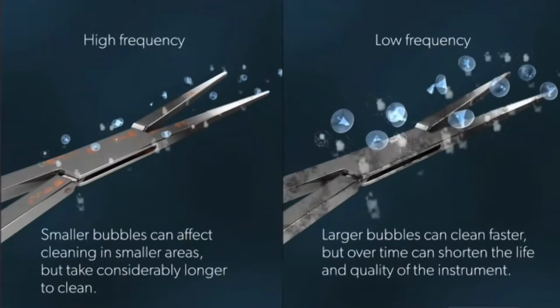Let's break down this cavitation energy, particularly in this case from the bonded transducer. I'm sorry, the titanium rod transducer, the rod form of your speaker. In terms of high frequency, smaller bubbles can affect cleaning in smaller areas, but take considerably longer to clean. Okay, so higher frequency, still ultrasonic, but much higher than, say, lower. And these bubbles can get into spaces much more finite in size, but they're small, so their impact is less than if there was lower frequency where larger bubbles are formed. Larger bubbles have much greater cleaning power in less time. Smaller bubbles take considerably longer to clean, and time is precious.